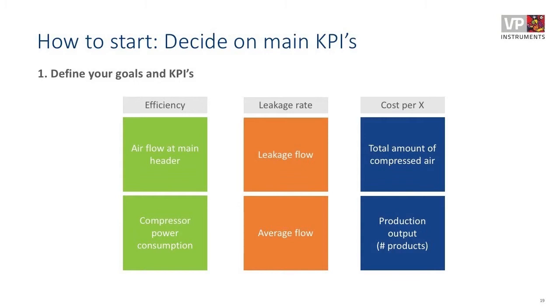Then the leakage rate: how much leakage flow is in my factory, for example, during lunch breaks, during the change of the day shift to the night shift, or maybe in the weekend. Take that number and divide it by the average flow during production. So you get a percentage of how much is leaking, or you can convert it to money, how many dollars this is on an annual or on a weekly basis.